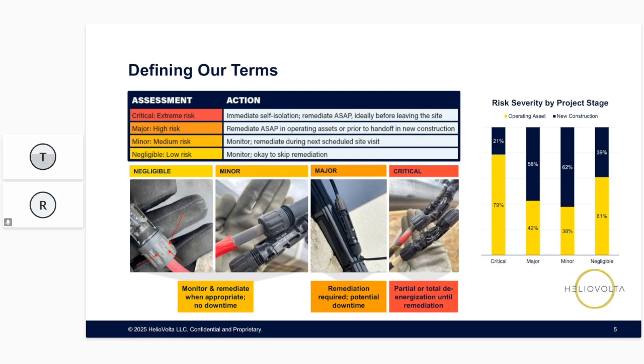Now, to be clear, I think these 2 issues matter. It's possible the integrity of these connectors has been compromised. There could be moisture ingress. This could cause overheating. There might be an electrical fault. It's a problem, but it's not an imminent threat. There aren't any thermal anomalies. We just need to keep our eyes on these connectors over time until it makes sense to fix them.